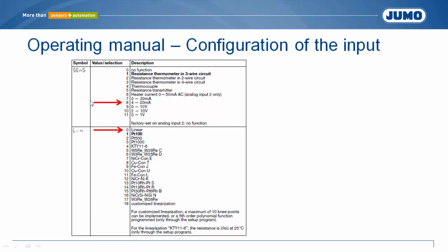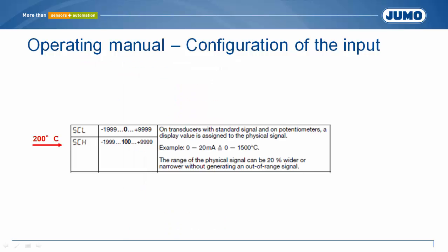For input 1, the signal 4 to 20 mA has to be defined in the configuration level. It's a linear signal. The scale for the 4 to 20 mA input signal is set to 0 to 200 centigrades.